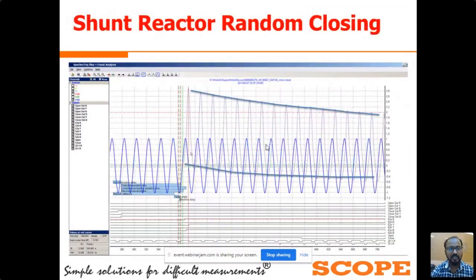Here you can see this is a waveform with the random closing of shunt reactor. This switching we have done without any reference of system voltage and system current. You can see the arcing current started near the voltage 0 point. In this continuous waveform, this is the system voltage waveform, and the waveform started at this point. This is the current waveform. This arcing current started to flow after closing of the CB contacts.